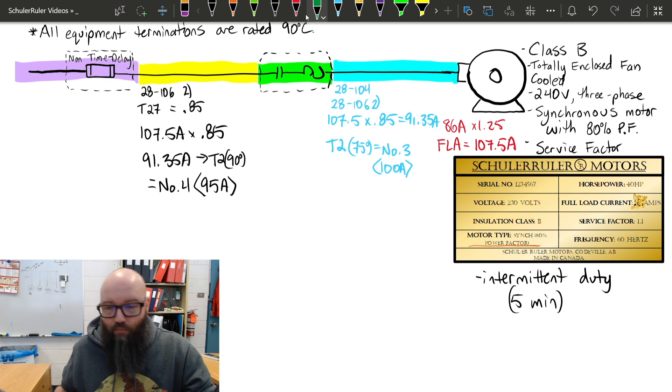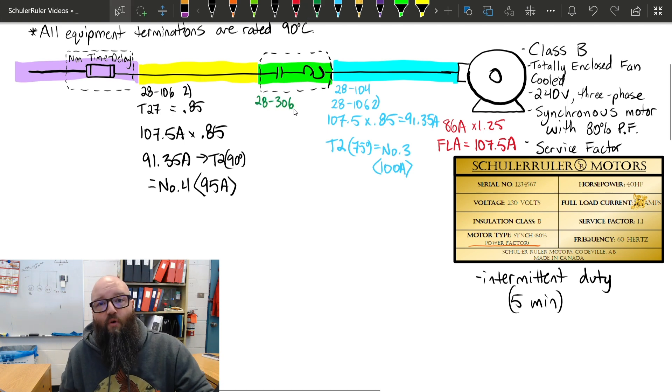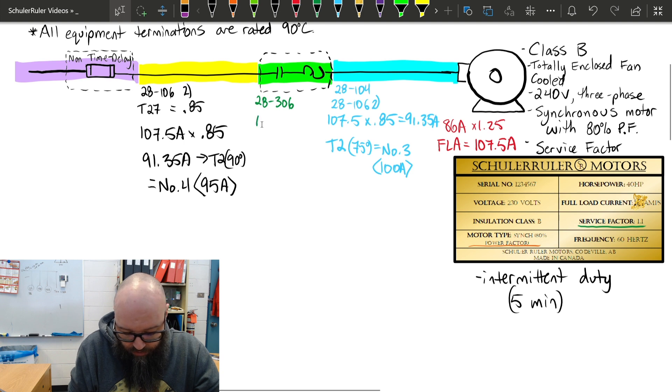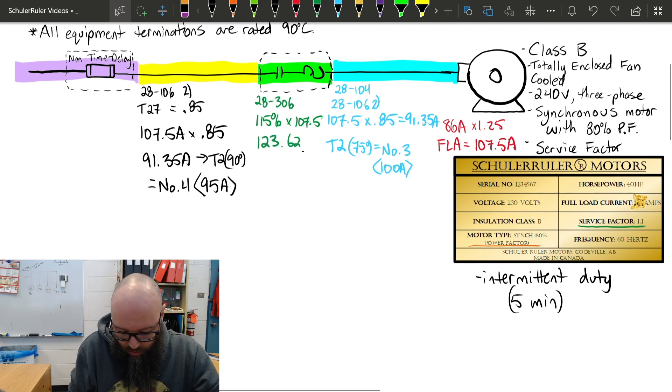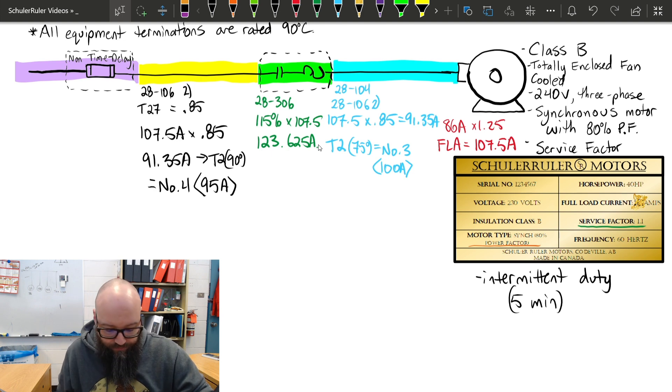Overloads, nothing changes there. We're still going to refer to 28306. It tells me for 1.15 or greater, I'm going to use 125%. In our example here, we have a service factor listed on our nameplate of 1.1, so for less than 1.15, we're going to use 115% as our multiplier times that good old FLA of 107.5 to get a maximum trip setting on that overload of 123.625 amps. If you could dial that up, that's the maximum you would be able to dial that up to for that overload according to 28306.